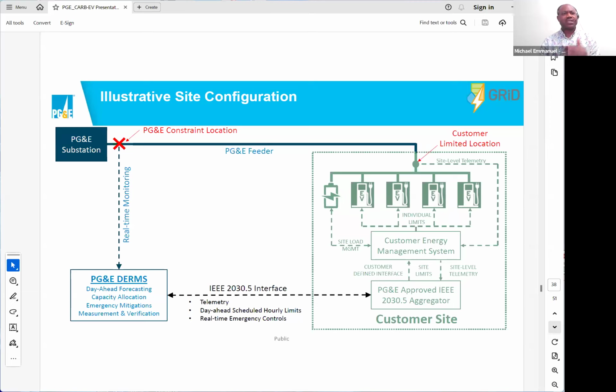Today, we're going to send a dynamic limit to the site for it to operate the next day. So we send a day-ahead scheduled hourly limit to the site. Now, to the right-hand side, the customer will have to have an energy management system at site that manages consumption. That's one of the requirements to participate in this kind of program. You need eligible, flexible load, and also a local site controller or energy management system to manage consumption at site. For this particular scenario, you have a combination of EV charging station and battery limit.